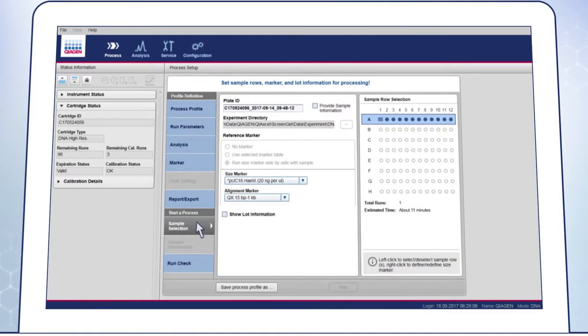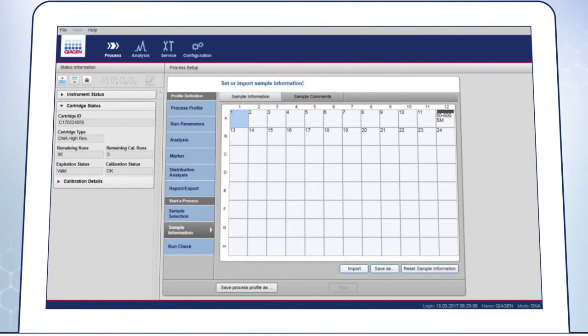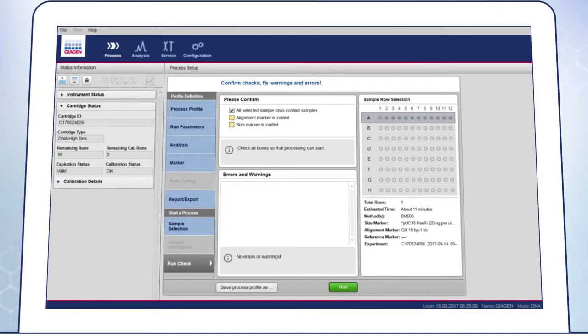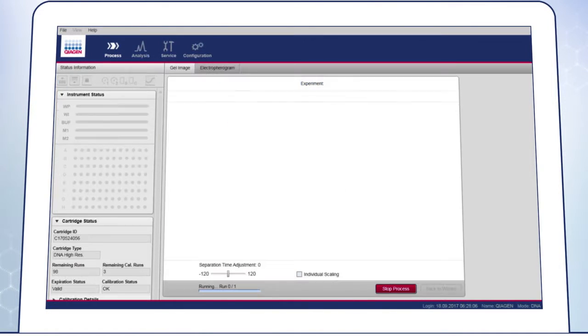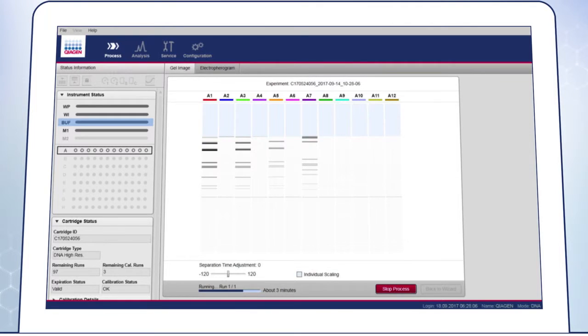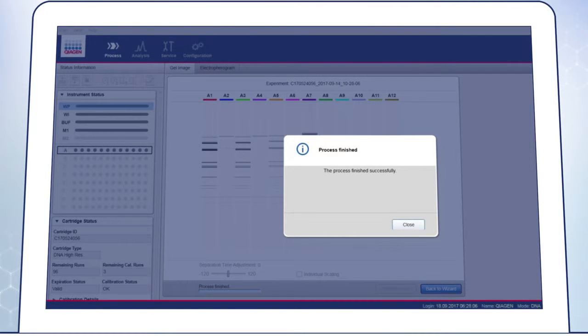On the Sample Selection screen, define the plate ID, which is also the later run file name. On the Sample Information screen, you can define sample names or import sample ID information. On the Run Check screen, you can get an overview of your settings, start the run, and check for any errors and warnings. If everything is fine, you can start the run. If changes are made in the parameters, the new profile can be saved.